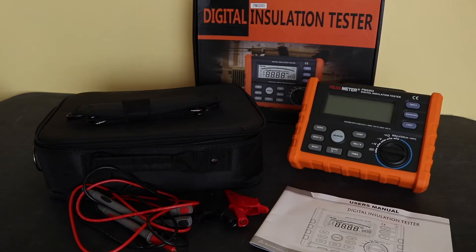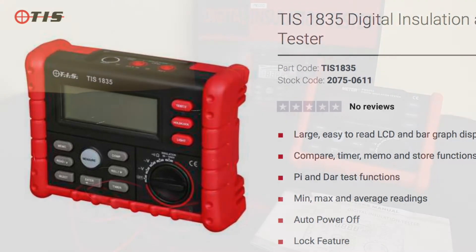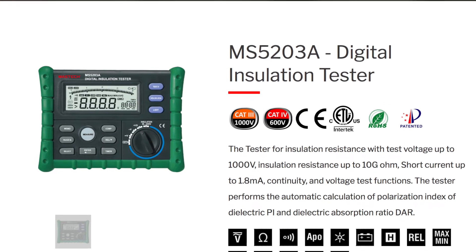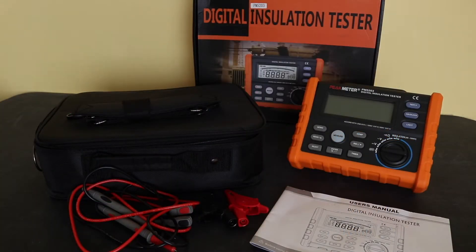At the upper end of the scale there's a version from Test Instrument Solutions, the TIS 1835, available from CEF and other electrical factors throughout the UK for anything from 200 to 300 pounds — but I believe it's still exactly the same unit as this PM5203. The only slight difference may be that Mastech also make an MS5203A, which has a 250 milliamp earthbond test to be compliant with IEC regulations. Some of those other units may be clones of that 5203A with a higher test current on the continuity function, whereas this unit only has a 1 milliamp test current, so it's not IEC compliant for earthbond tests.